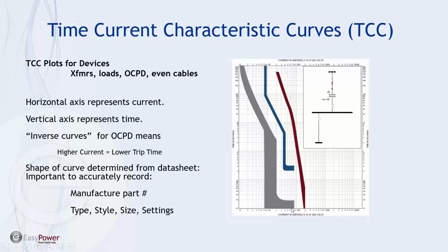These are similar to every other plot that we've ever seen in our education, the difference being we have current on the horizontal axis and time on the vertical axis, and we are in the process of doing a short circuit study. We're predicting the current that will occur on a specific bus downstream of a downstream fault. Now, the term inverse curves is applied to overcurrent protective devices, and it basically means the higher the current, again, the current's on the horizontal axis, then the quicker the response time of the protective device.